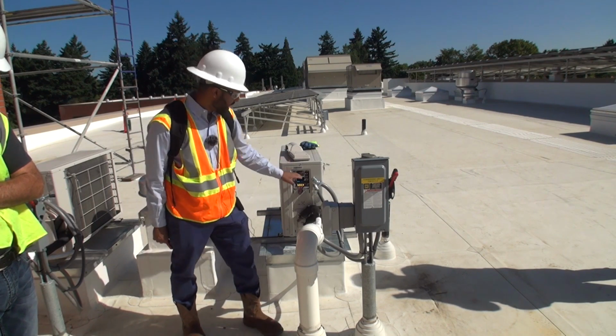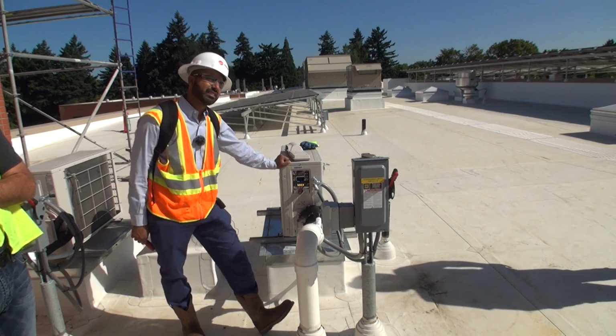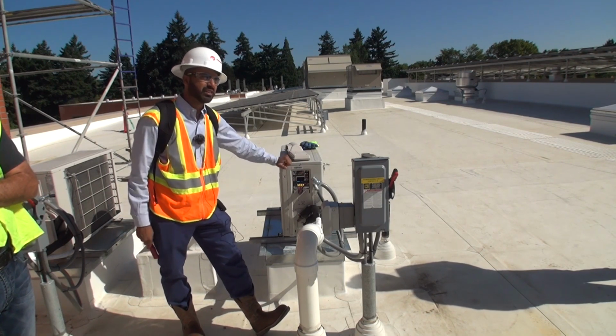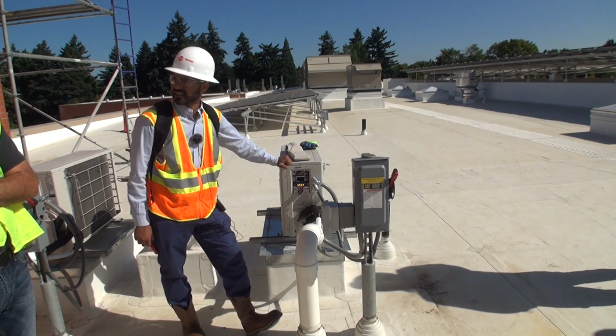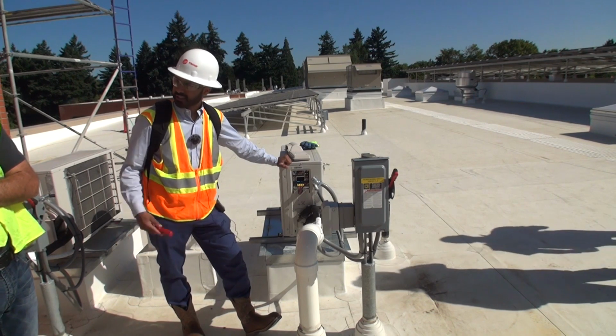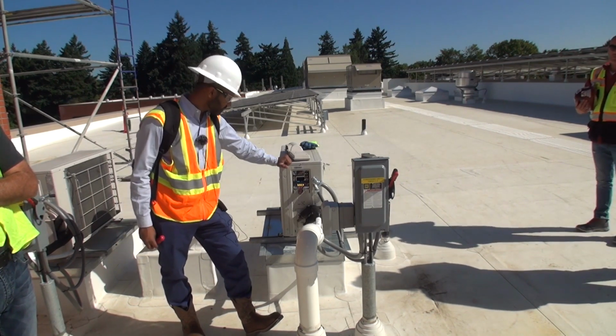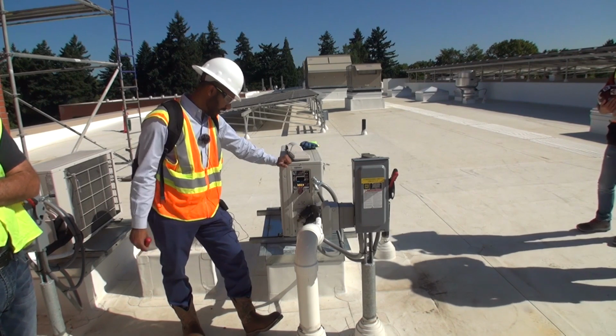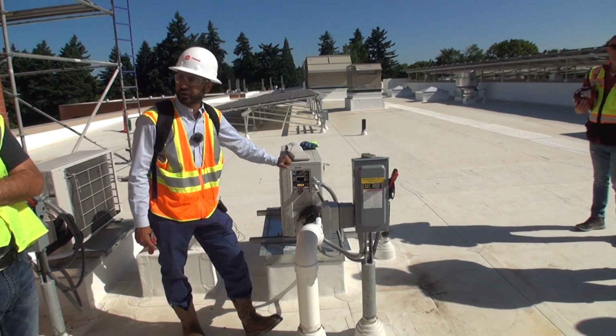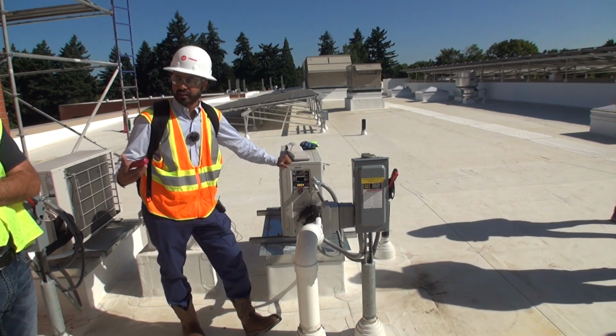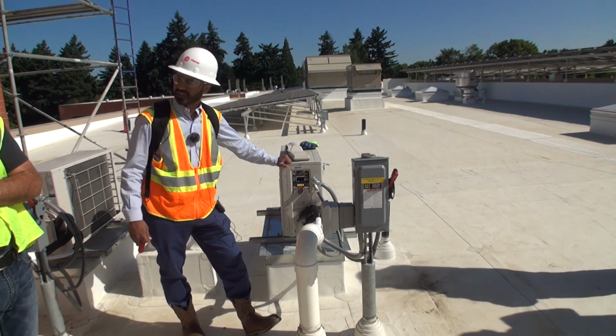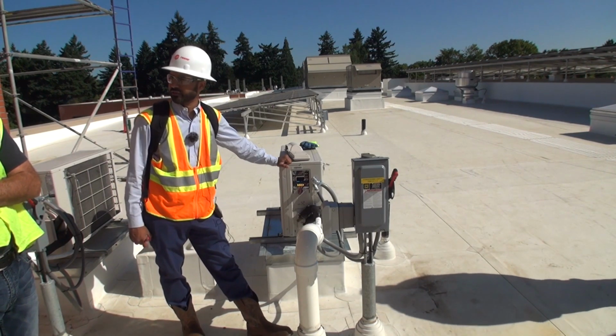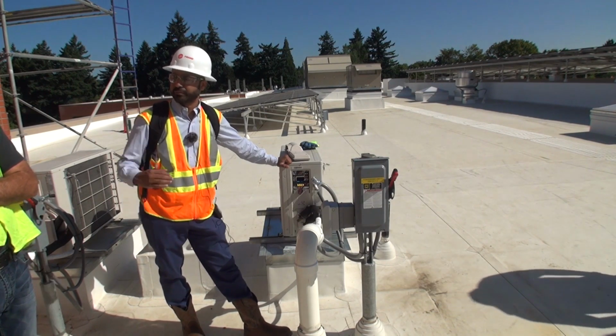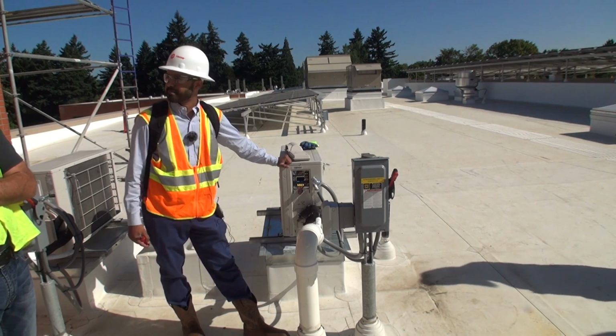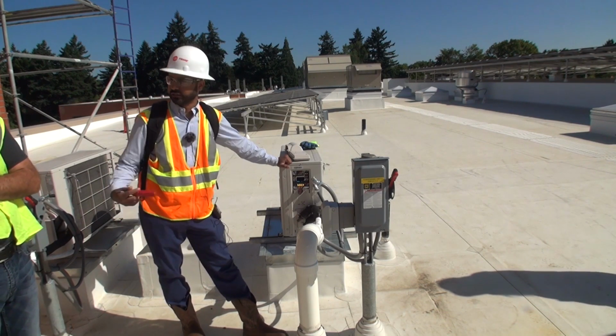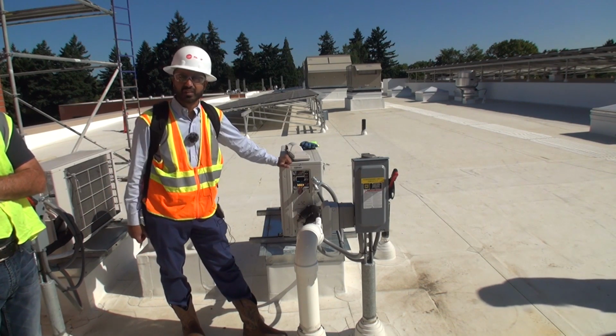One of the things you also have is your K3 button, which is kind of a reset - it's like booting up and booting down your computer. It'll be on our IOMs, it doesn't have it specifically on here. So when you have the ability to do all that, when you see an error code, sometimes it just happens on the coldest day of the year - you'll have like a high top compressor sensor give you an error. Not really an error, the system's just beyond its operating range, so you might have to reset it. You might have to come out here, hit the K3 button, and it'll just go back to its normal operating mode.